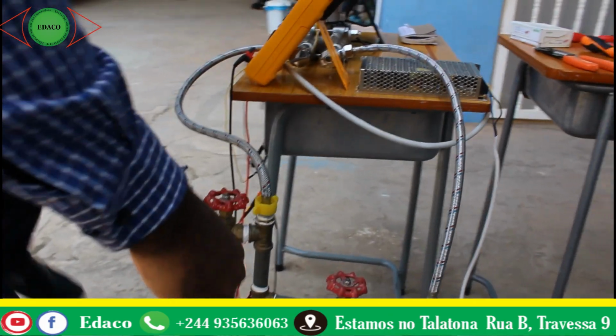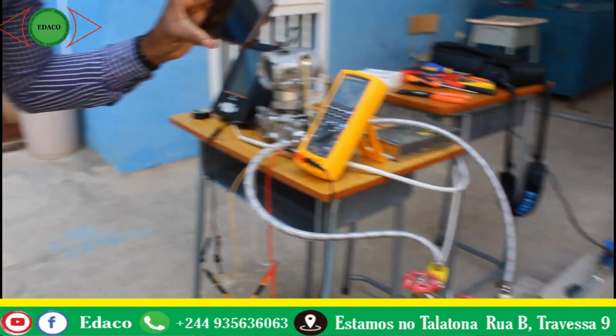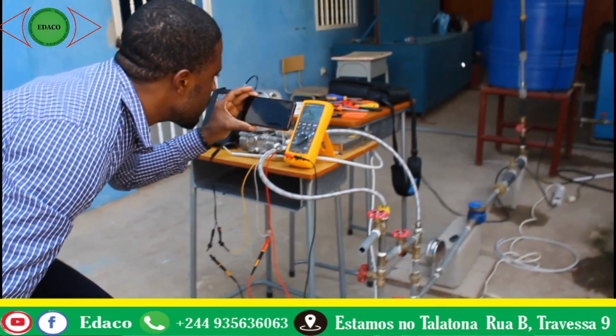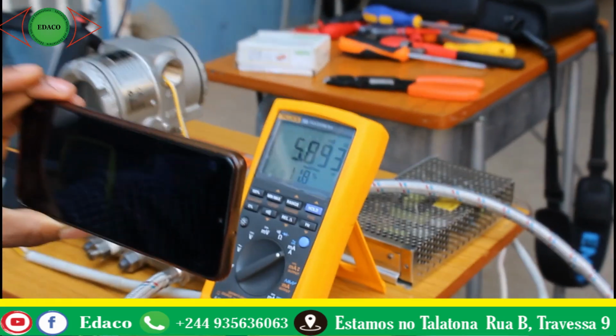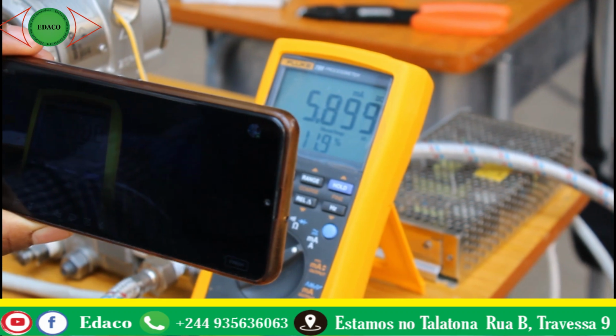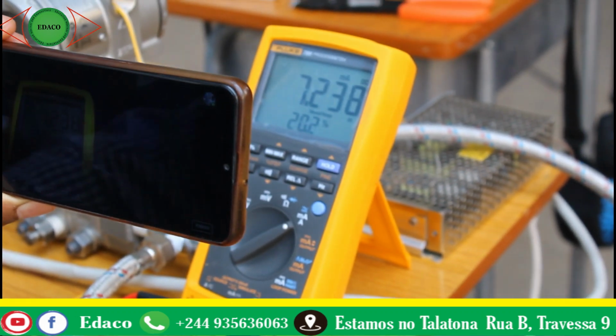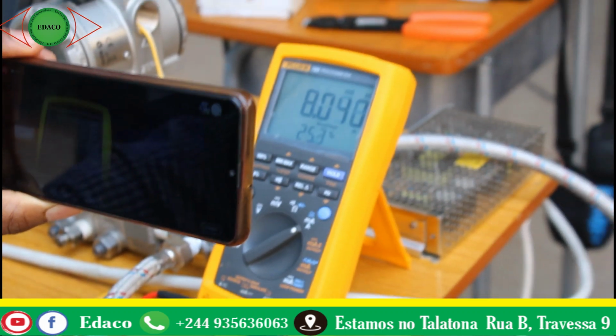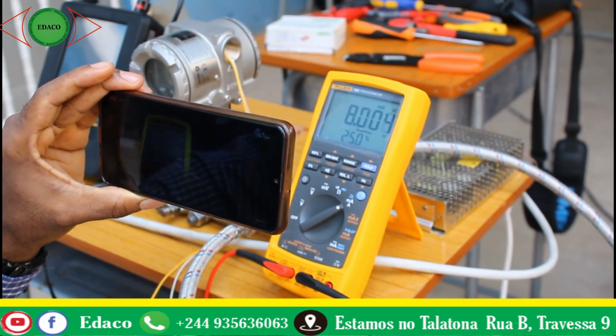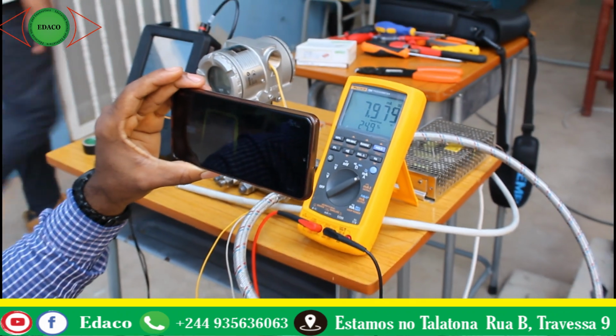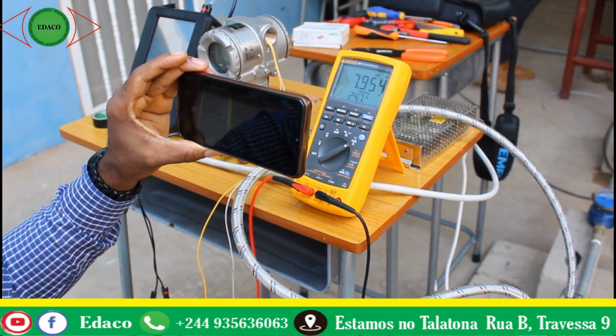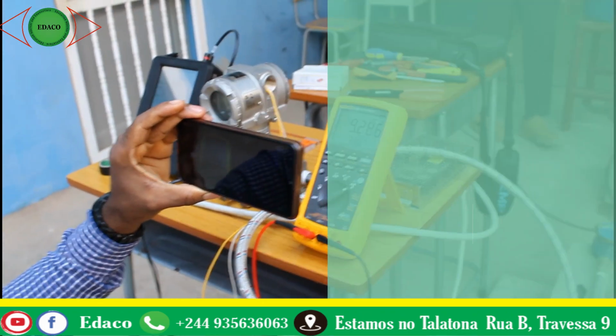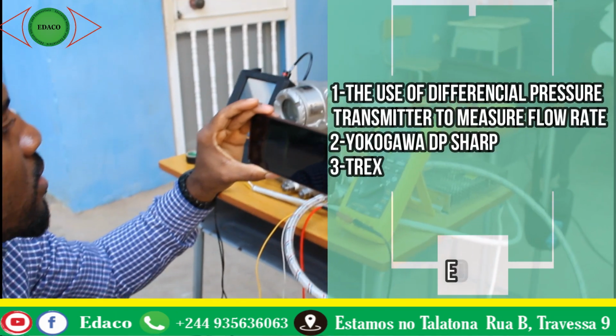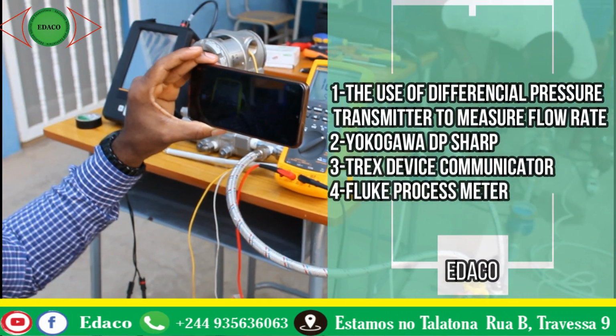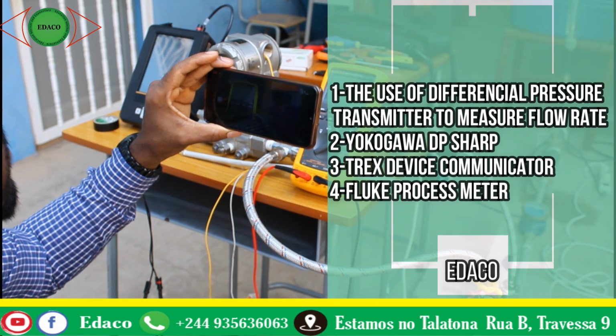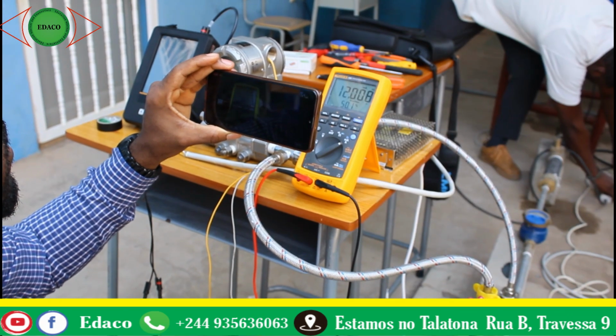I'm just going to increase the flow in the system, and you're going to see the percentage come up. Of course, the signal of our transmitter is going to increase as well, and the pressure. So now we are reading, let's try to put it at 50%.